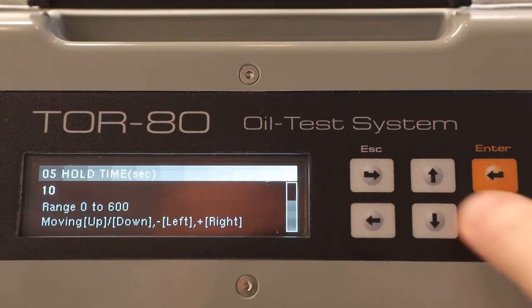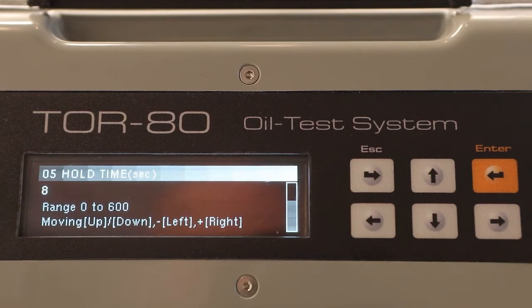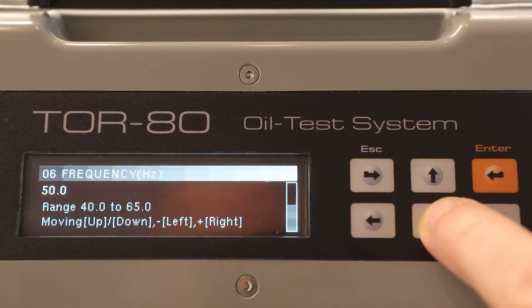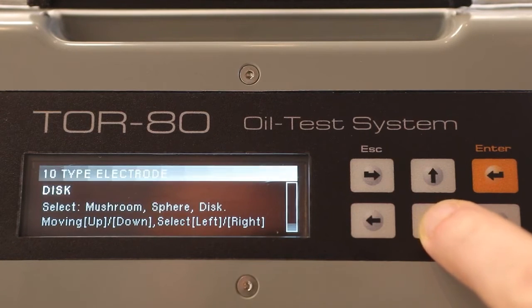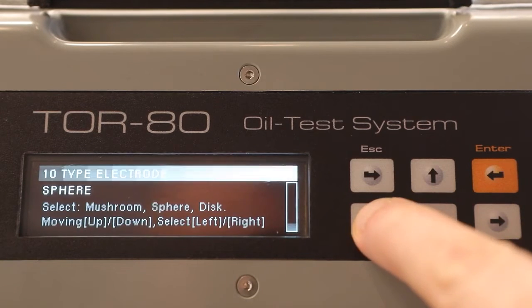You can also change the duration of hold time — the time from the end of stirring to the beginning of the next voltage rise. The third setting is the frequency and the limit of the testing voltage in hertz and volts, respectively. The type of electrodes and the distance between them in millimeters are also selectable; for measurements you can use mushroom, spherical, or disk electrodes.